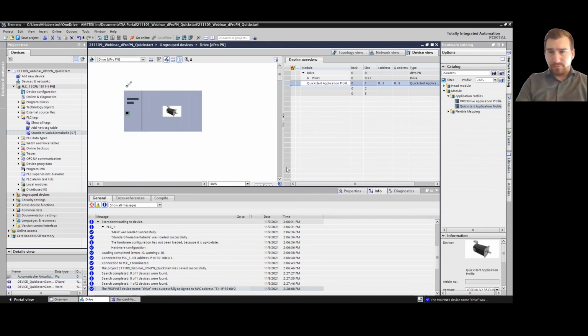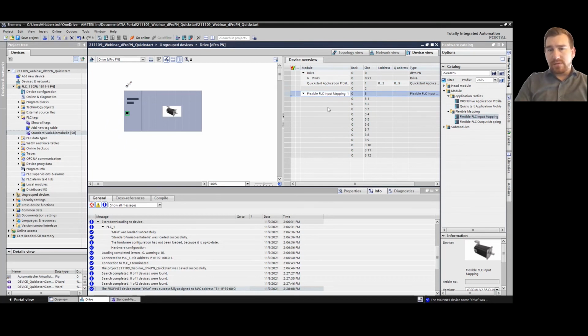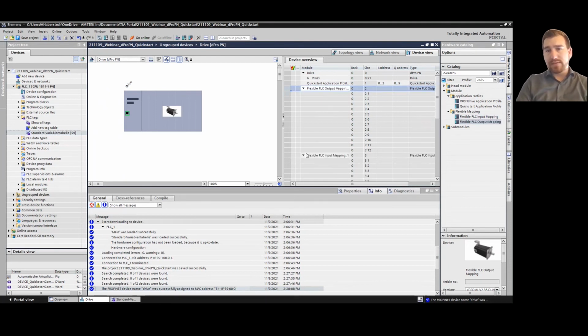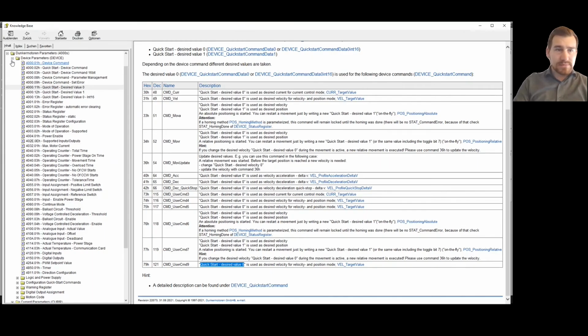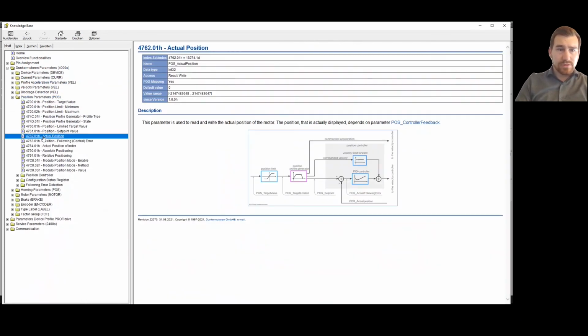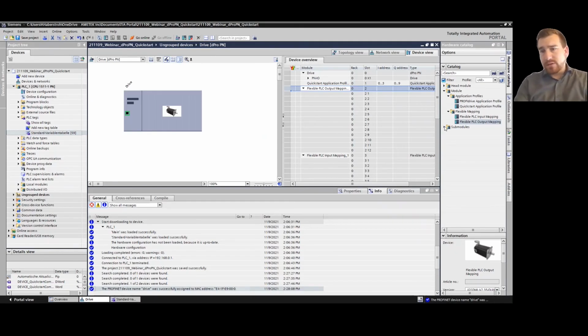possibilities with the motor. First of all, we have the flexible mapping here. There you can add up to 12 objects in the cyclic data as input data and also 12 motor objects in the cyclic data in the output mapping. For example, we could use it for the position. If we have a look into our knowledge base, we have the position here, and the actual position is an int 32 value, and this is the name. I will copy it for later. So we want to read the actual position. Therefore, we have to use the input mapping.